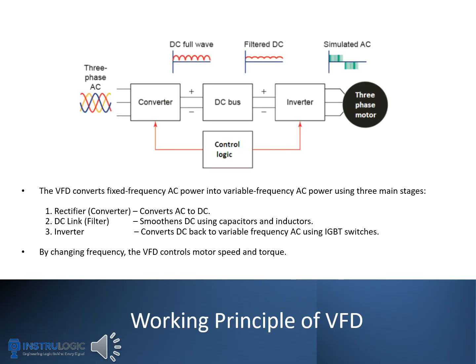A VFD converts fixed-frequency AC power into variable-frequency AC power. This process happens in three main stages. First, the Rectifier or Converter converts AC power into DC power. Second, the DC Link or Filter smooths the DC using capacitors and inductors to remove ripples. Third, the Inverter converts the DC back into AC, but with a variable frequency and voltage, using IGBT switches. By changing the frequency of the output AC, the VFD controls the speed and torque of the motor.